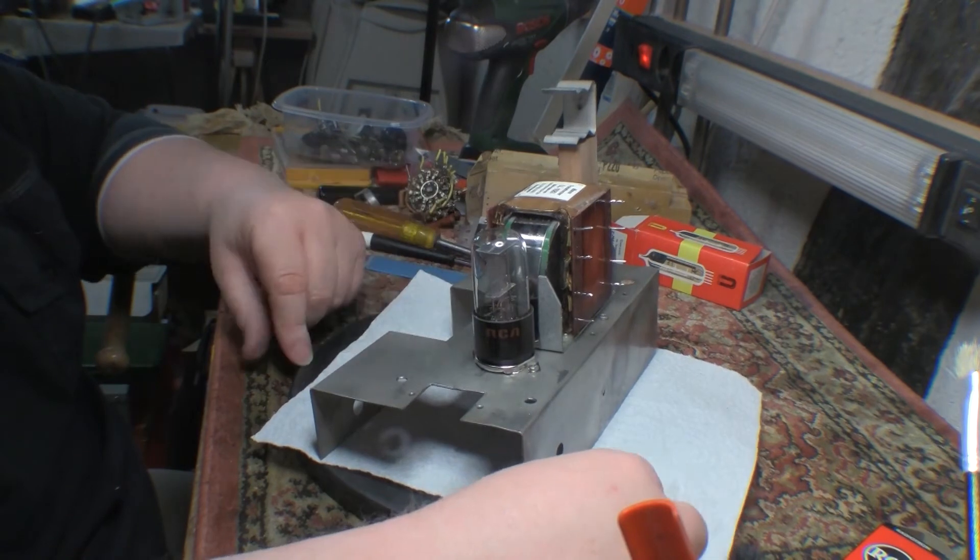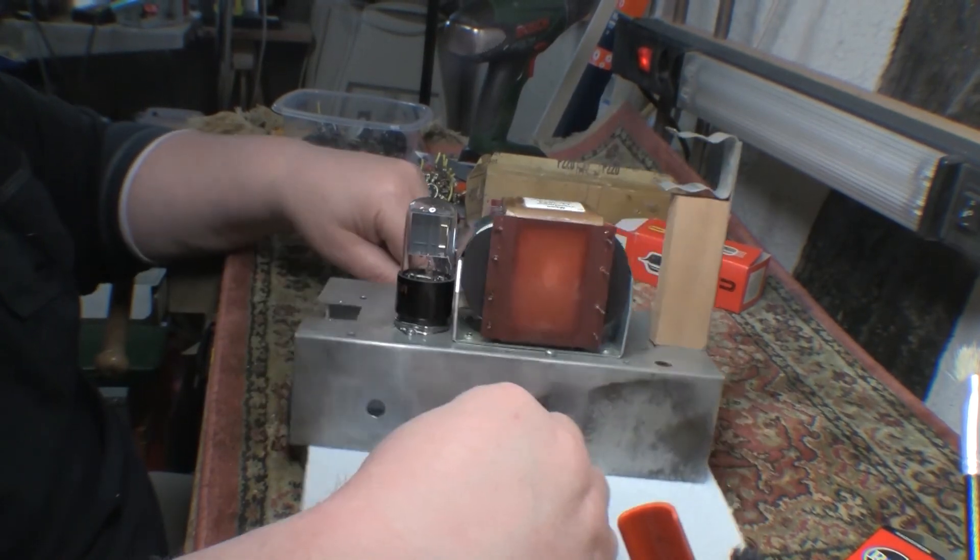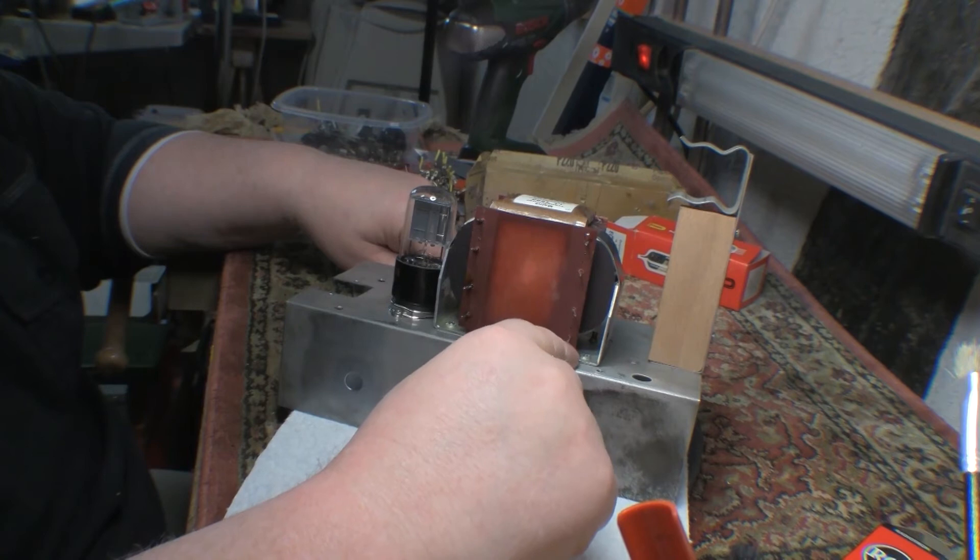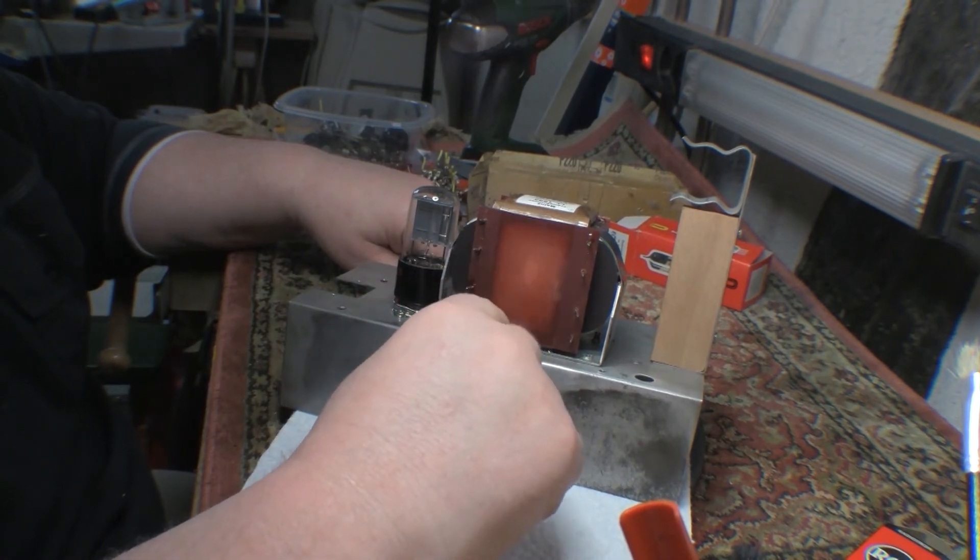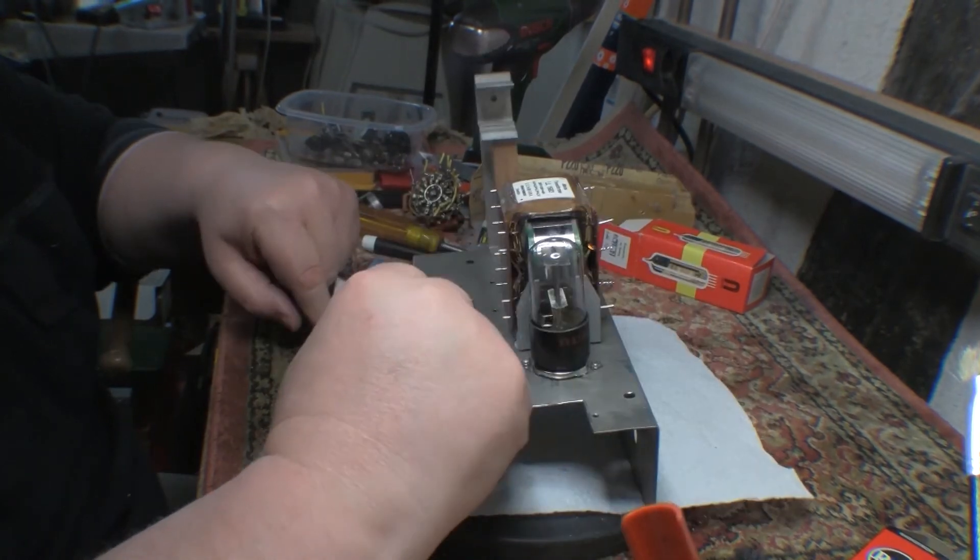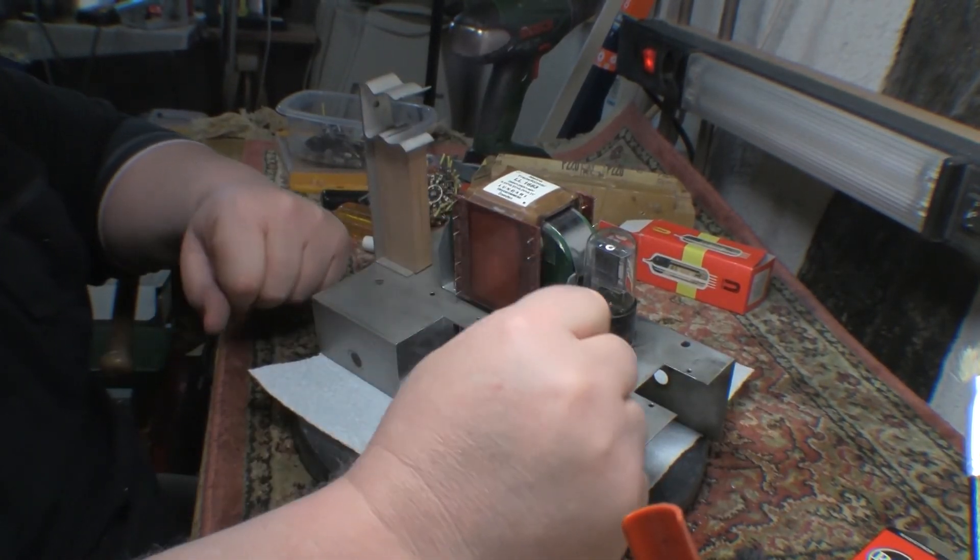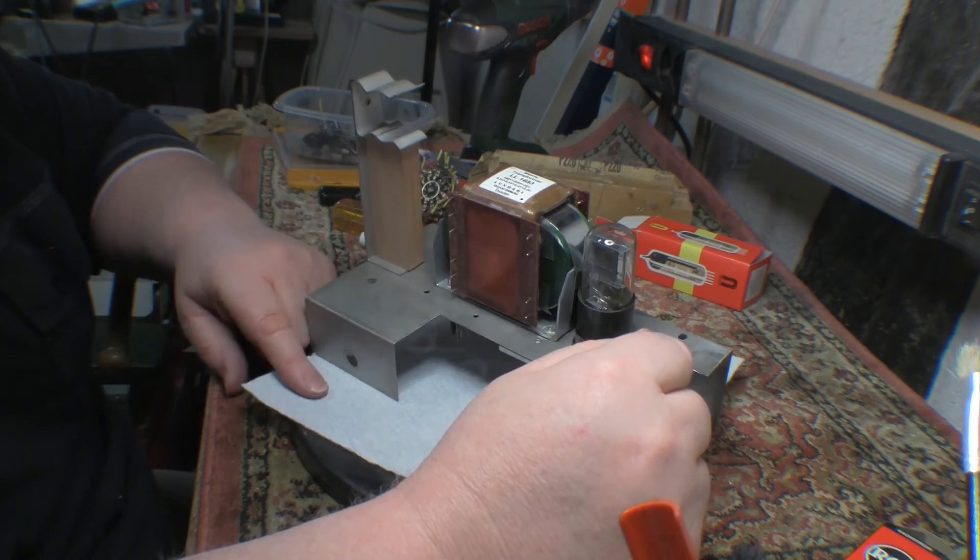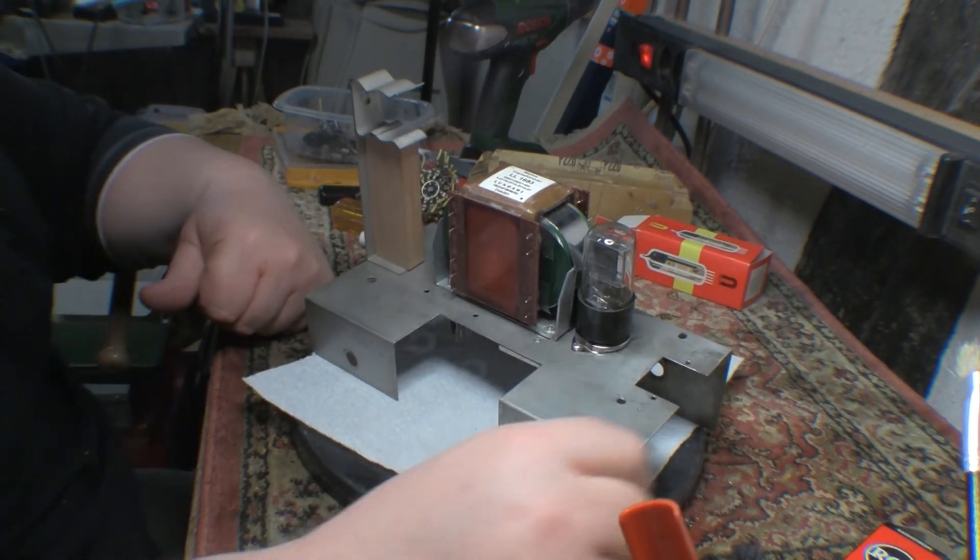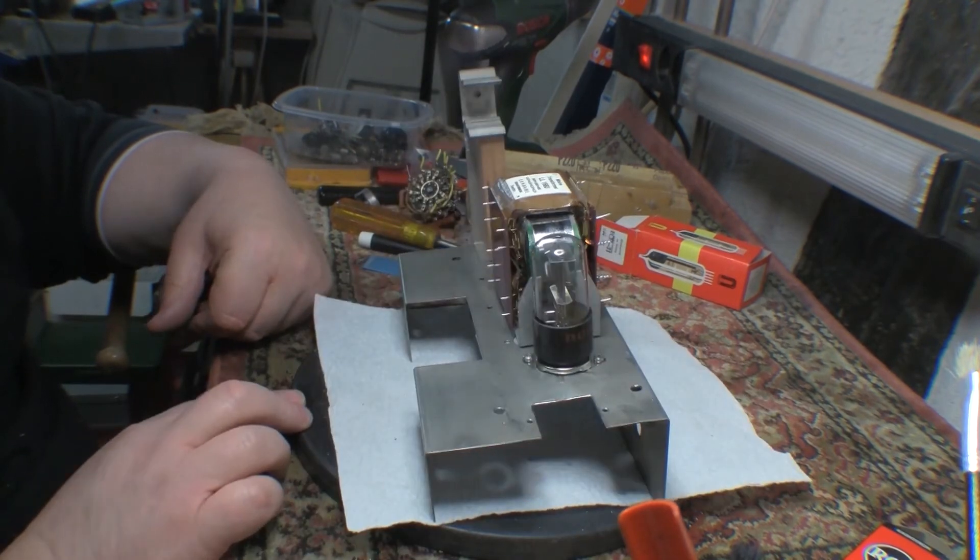The other thing I think I'm going to do is make a real-time one-to-one drawing of the pinouts on the transformer and stick it on here, front and back, just to make sure I don't make any mistakes when it comes to turning the theory into the practice.